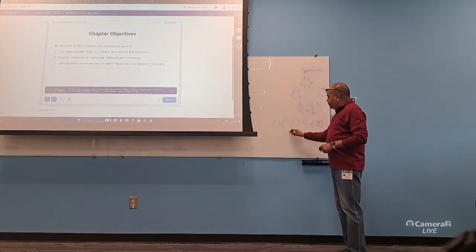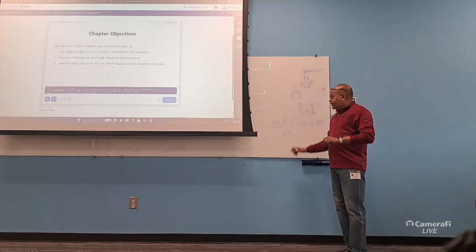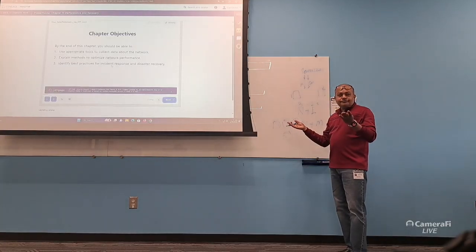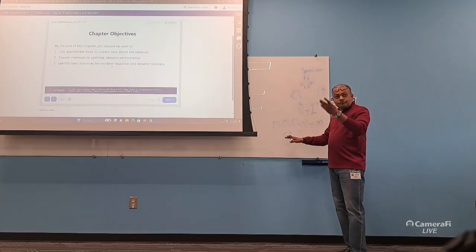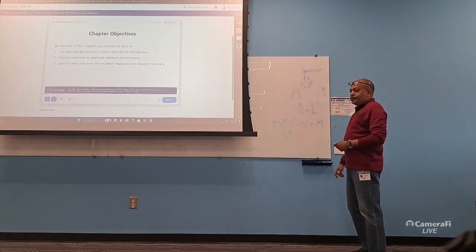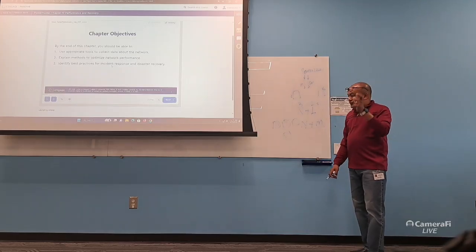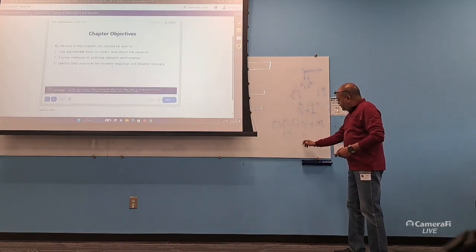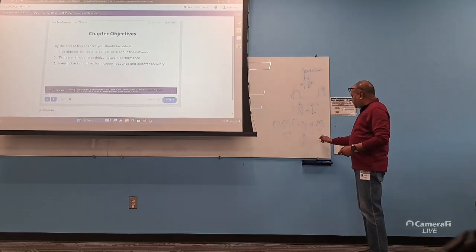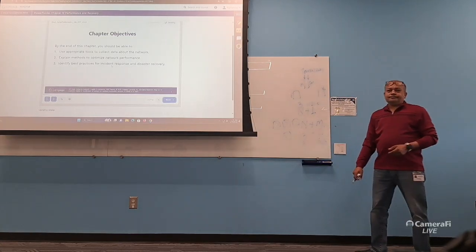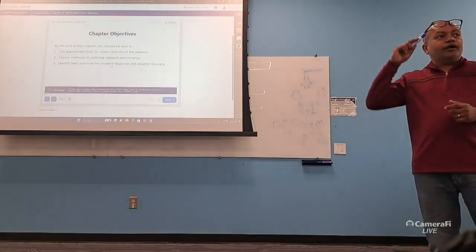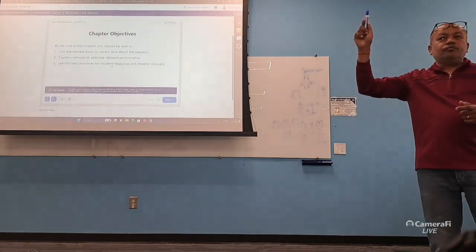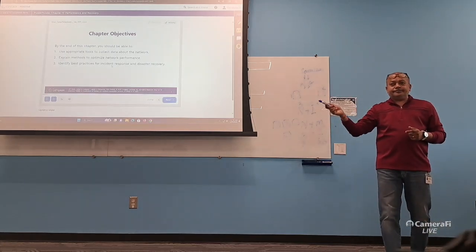If 1 fails, then I will use this one, right? If this also fails, this is already failed, but this also fails. What happens then? Can I run my operations? Oh, no. Then N plus M comes. You will use 3 for the active operation but you will keep 2 for the standby. 2 for the standby. Because you are anticipating a situation where more than one genset fails.